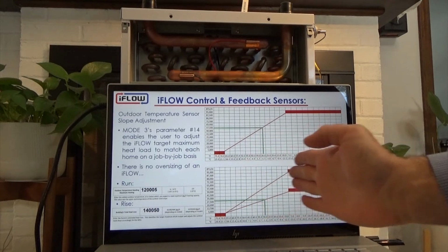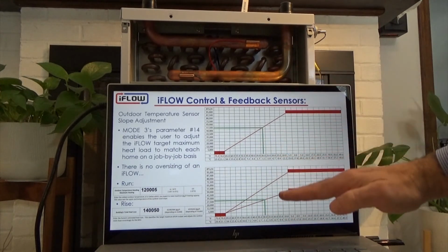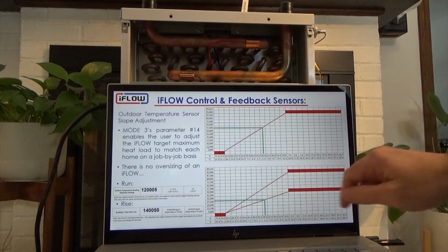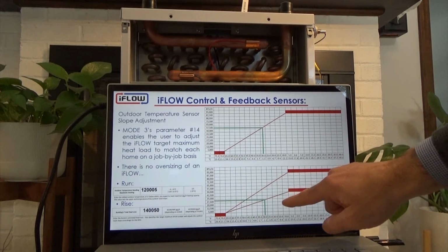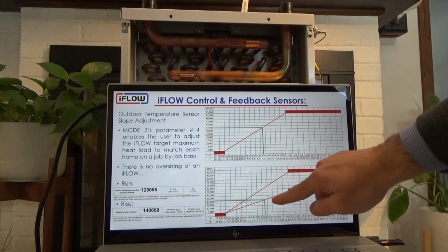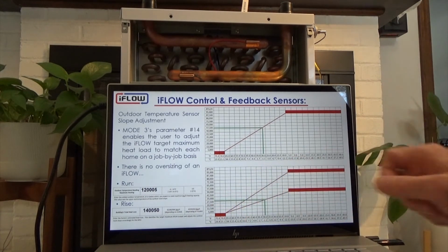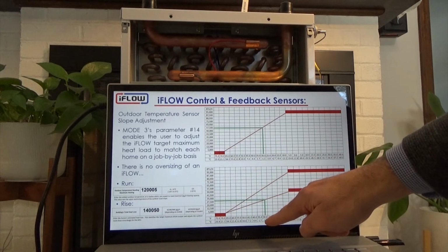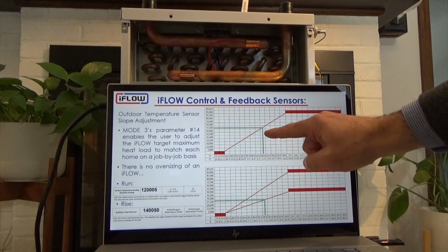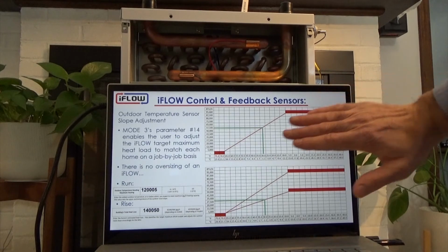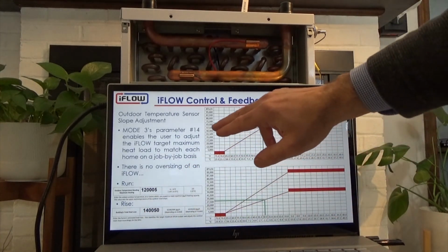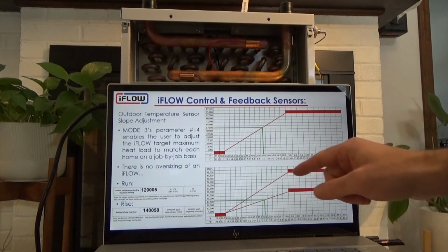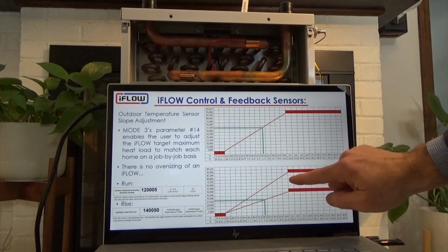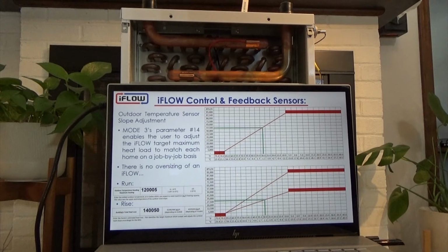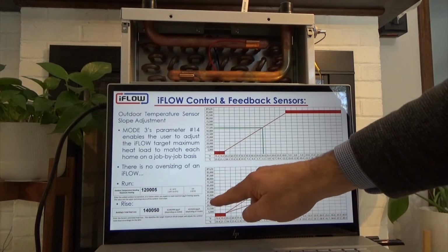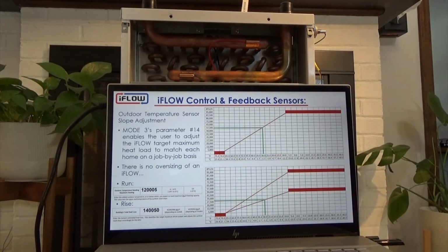So that will skew the curve left or right, and then your heat loss will increase or decrease the rise, such that we get a different slope. So when we program in that lower input, we see that it actually changes the slope of the curve significantly, and that will change the amount of BTUs we deliver significantly. For example, using that same temperature design, the 30 degrees outside or -1 Celsius, if we did not adjust the maximum input at parameter 14, then we'd be delivering 57,500. But because we've lowered the slope of the curve by inputting our actual correct heat loss for that specific house, now we're only going to be delivering, at that same outdoor temperature, 27,500 BTUs.